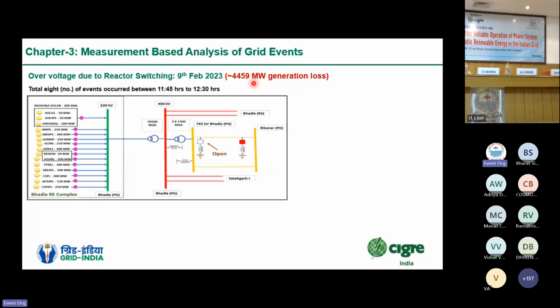Now coming to the next category, which is over voltage due to reactor switching. On 9th of Feb 2023, we witnessed 8 generation loss events within a span of 45 minutes. On the opening of a line reactor of Bhadla Bikaner 765 kV line, we saw a rise in voltage. That voltage rise did not reach near the HVRT limits, but still we observed generation loss.